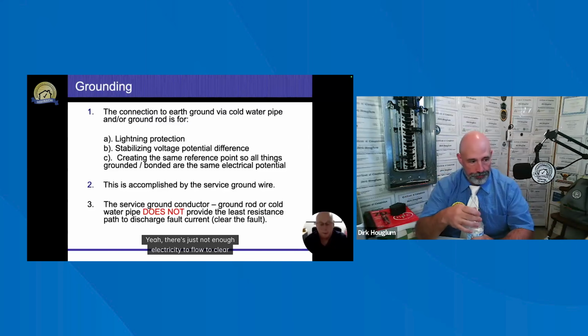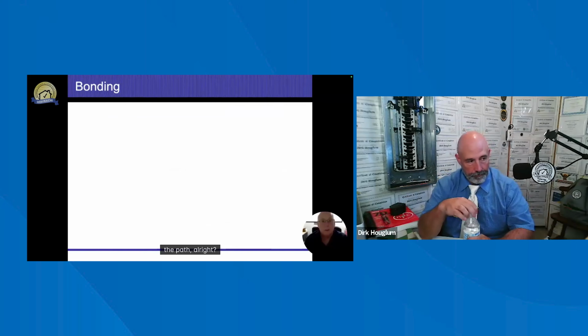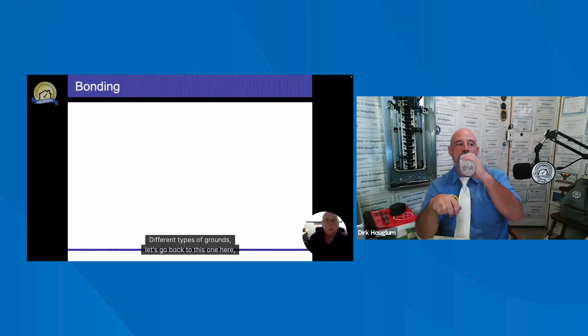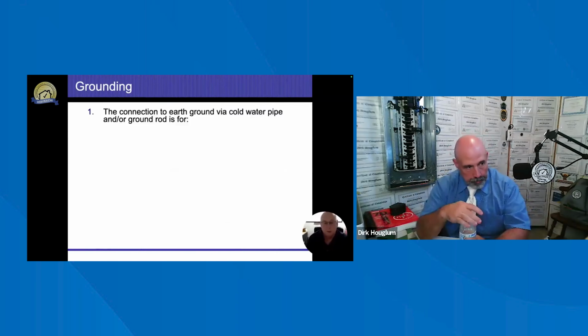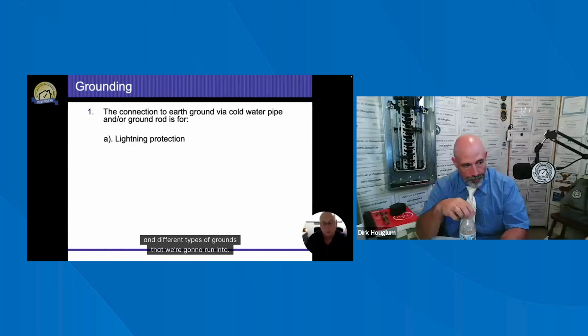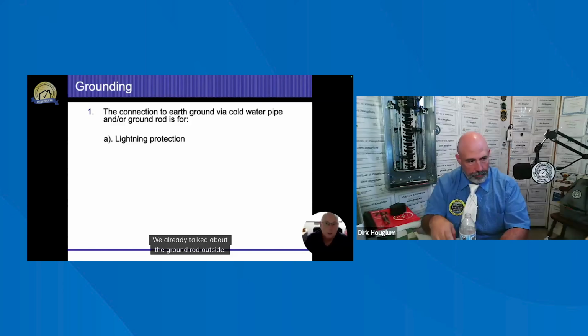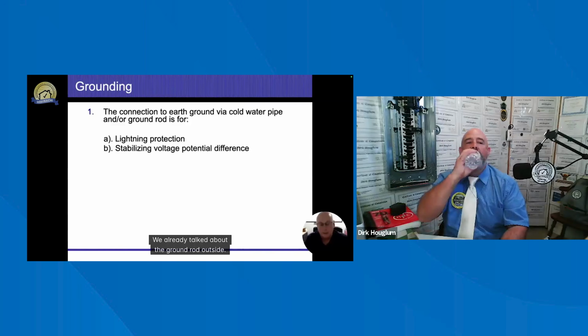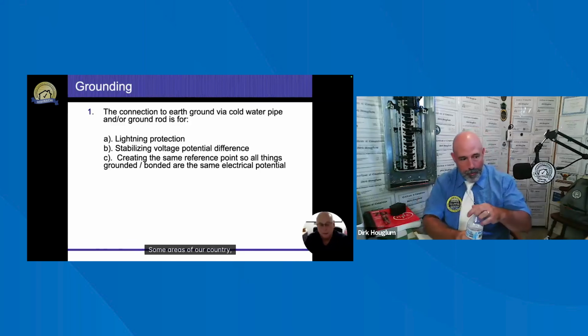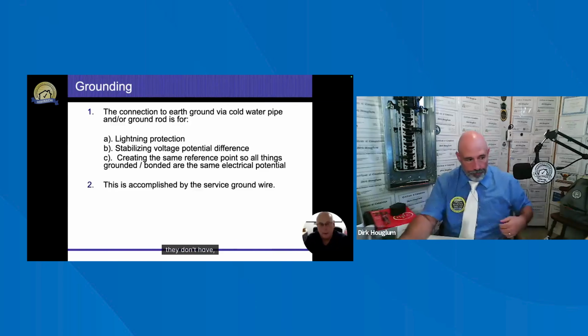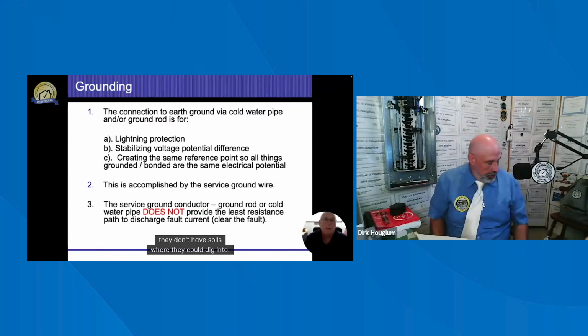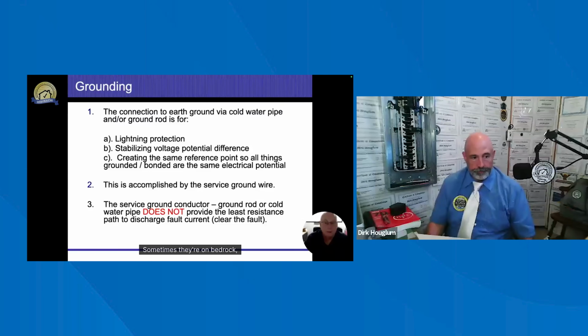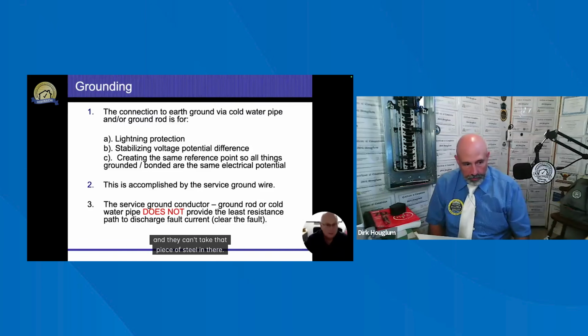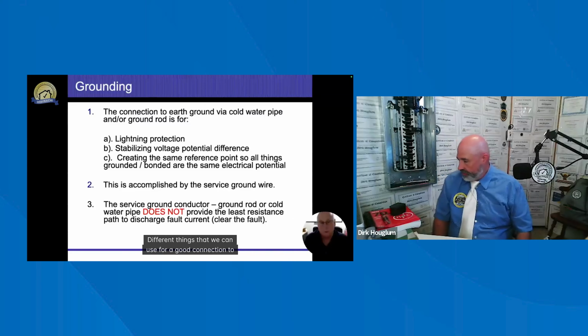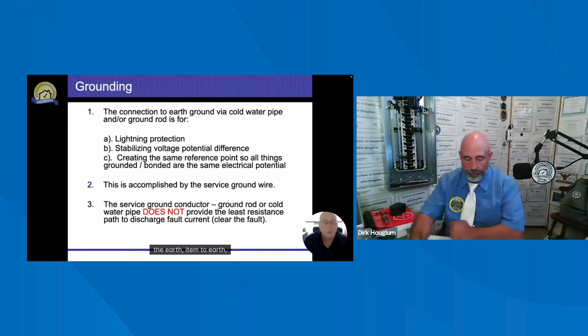There's just not enough electricity to flow to clear the path. All right. Different types of grounds. Let's go back to this one here, the different types of grounds that we're going to run into. So here it mentions the water pipes. We already talked about the ground rod outside. Some areas of our country don't have soils where they could dig into. Sometimes they're on bedrock and they can't put that piece of steel in there. Sometimes it's going to be on a slab. There are different things that we can use for a good connection to the earth.